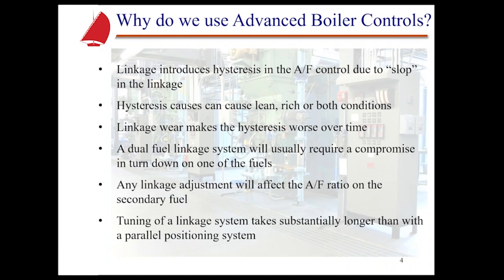And a dual fuel linkage system will usually require a compromise in turn down on one of the fuels. In particular, if you have a gas oil type burner, the low fire point is usually dictated by where the oil will fire at low fire, not giving you that advantage of greater turn down on the gas. So the linkage really is a compromise in that type of application.